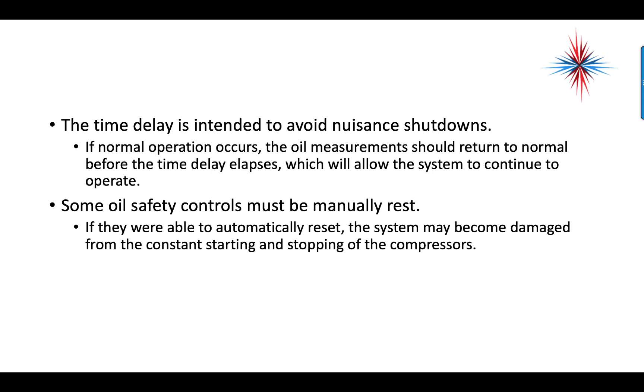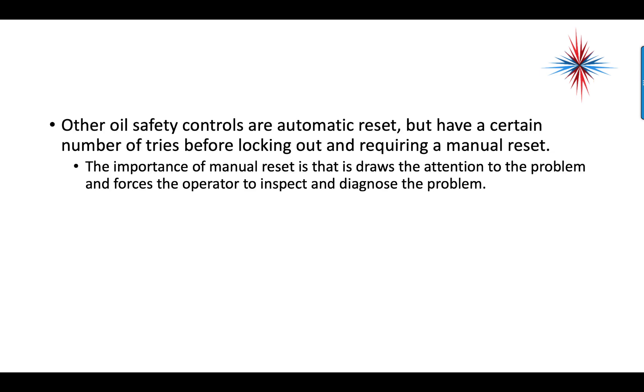Some oil safety controls must be manually reset. If they were able to automatically reset, the system could become damaged from the constant starting and stopping of the compressors in a low oil situation. Other oil safety controls are automatic reset but have a certain number of tries before locking out and requiring a manual reset. The importance of a manual reset in any of these safety controls is that it draws attention to the problem and forces the operator to inspect and diagnose it.